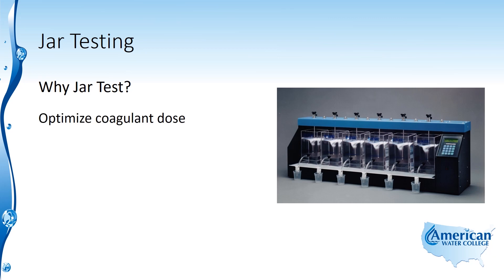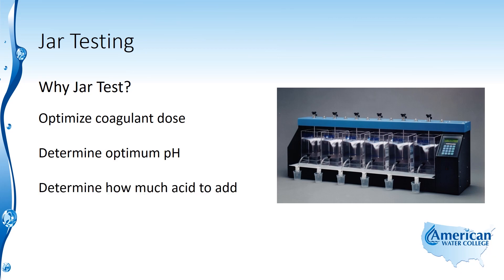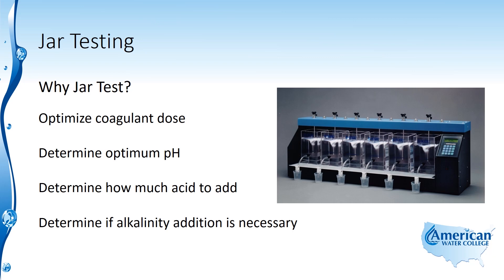One reason for jar testing is to optimize the coagulant dose, done for the purpose of treating water at the lowest possible cost but also for the best coagulation and flocculation for maximum material removal. Jar testing can also be used to determine the optimum pH for the coagulation process, and it will help us determine how much acid we need to add during the enhanced coagulation process.